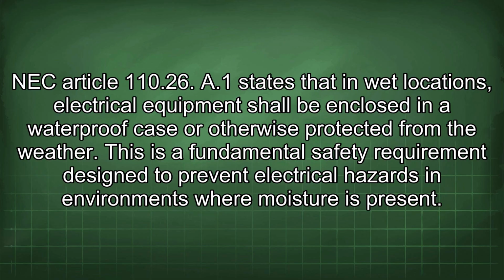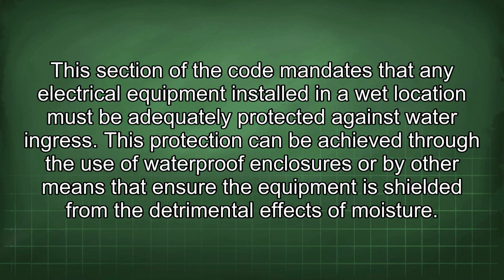the weather. This is a fundamental safety requirement designed to prevent electrical hazards in environments where moisture is present. This section of the code mandates that any electrical equipment installed in a wet location must be adequately protected against water ingress. This protection can be achieved through the use of waterproof enclosures or by other means that ensure the equipment is shielded from the detrimental effects of moisture.